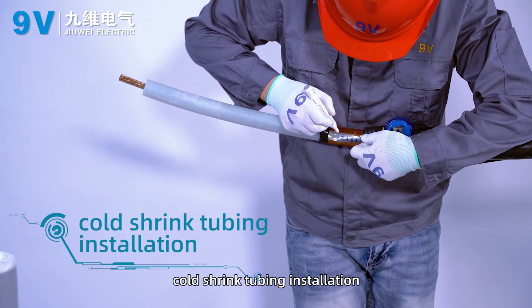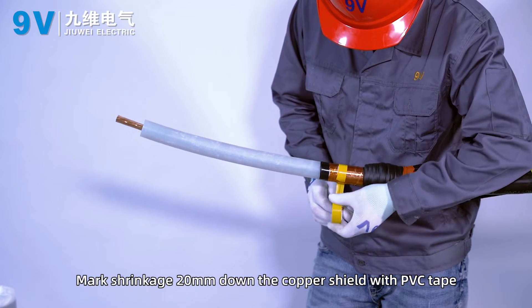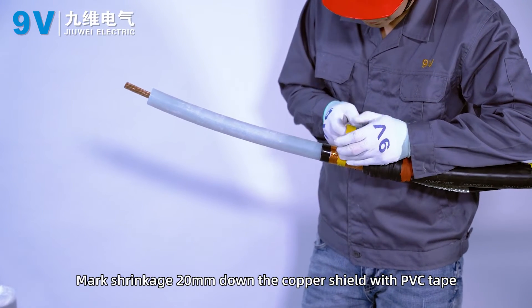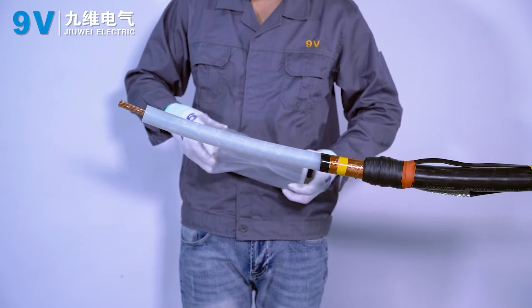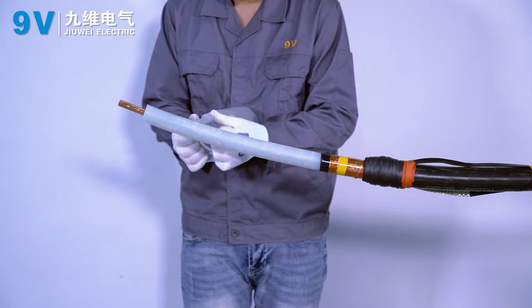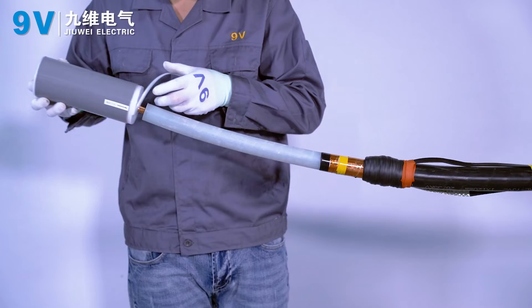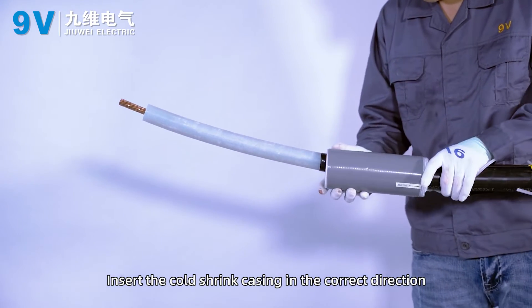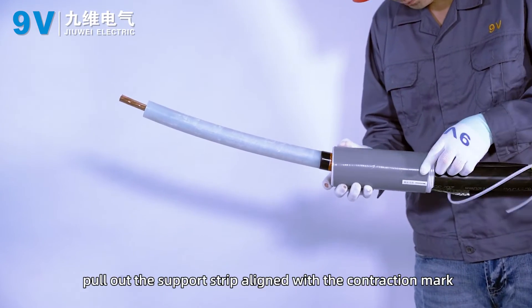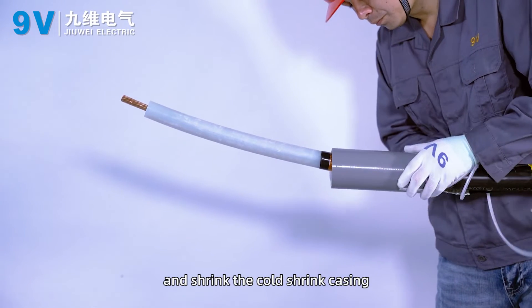Coat shrink tube installation. Mark 20 mm down the copper shield with PVC tape to indicate the shrinkage position. Insert the cold shrink casing in the correct direction. Pull out the support strip aligned with the contraction mark and shrink the cold shrink casing.